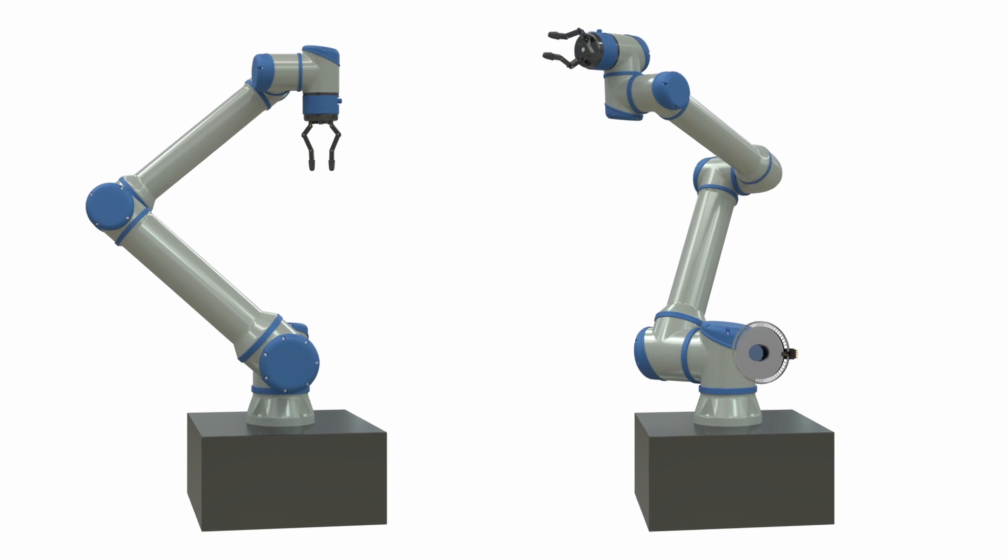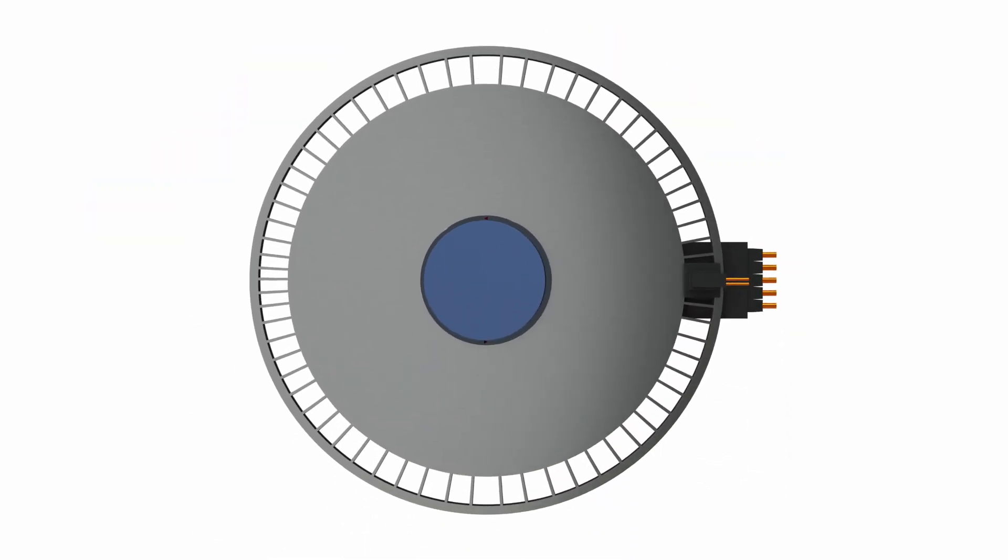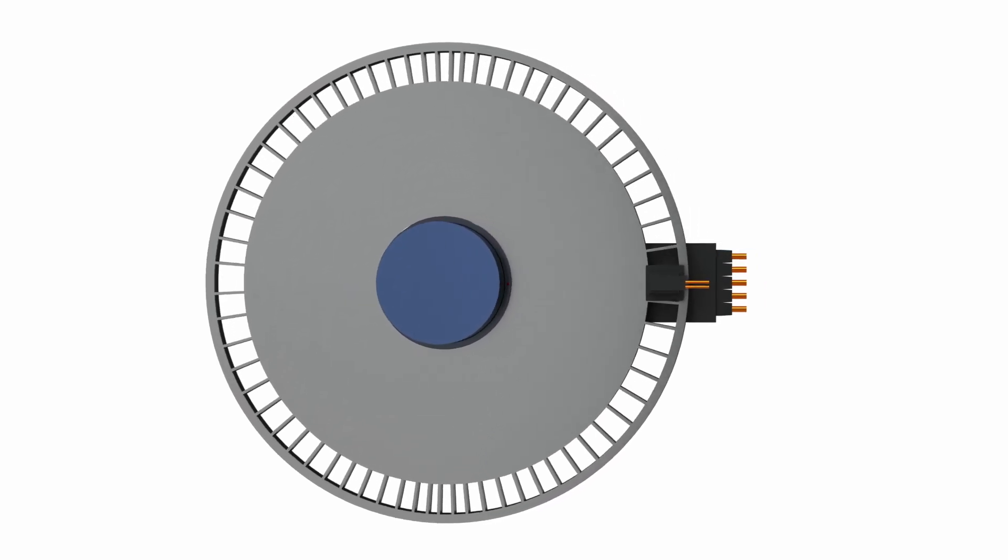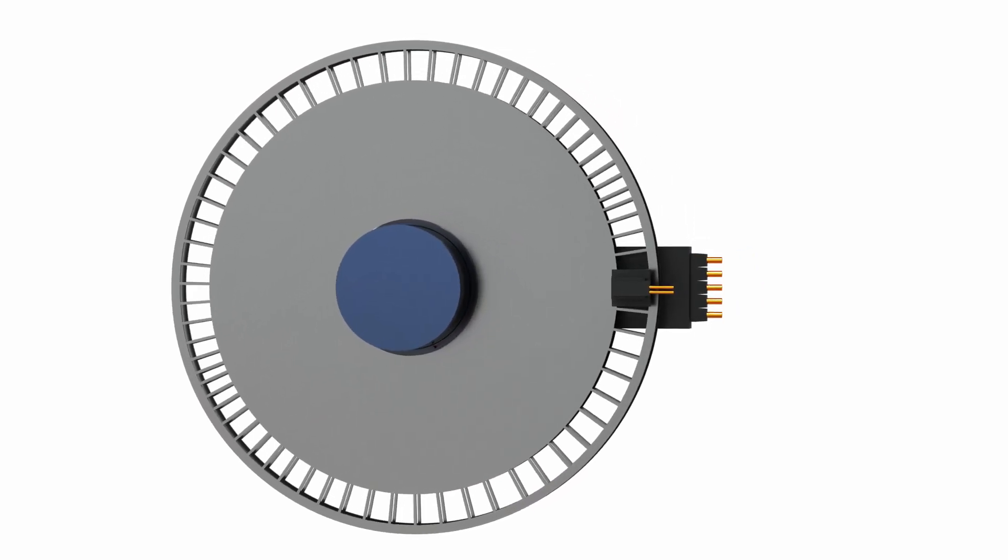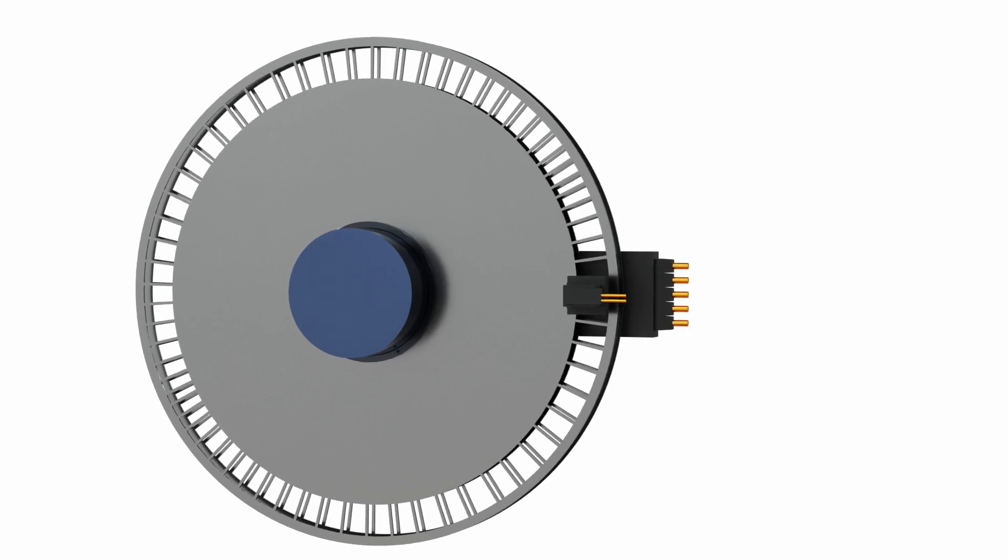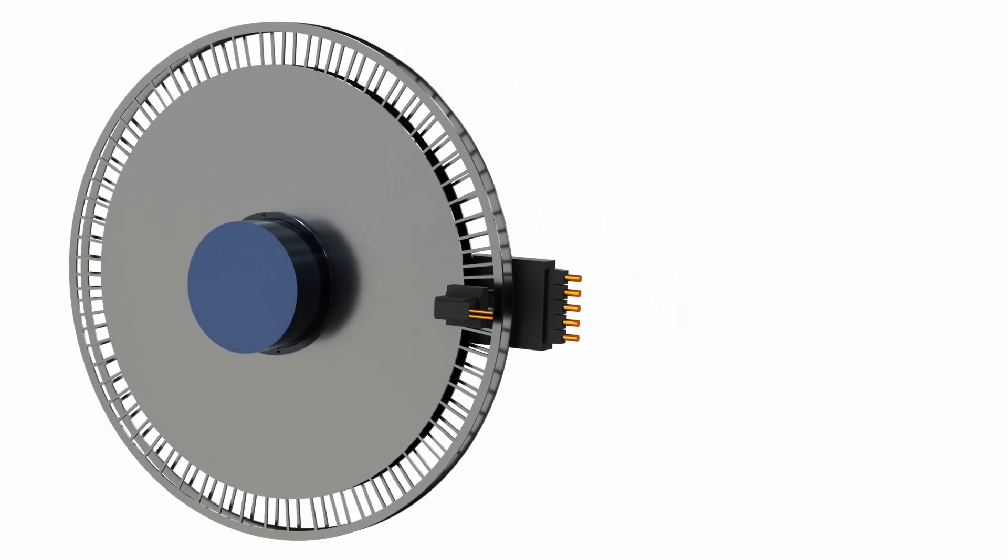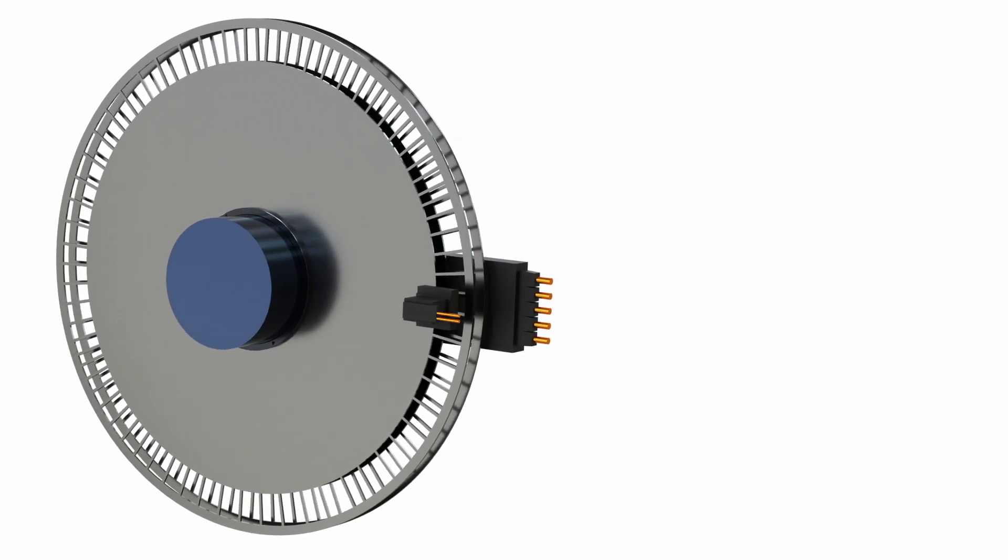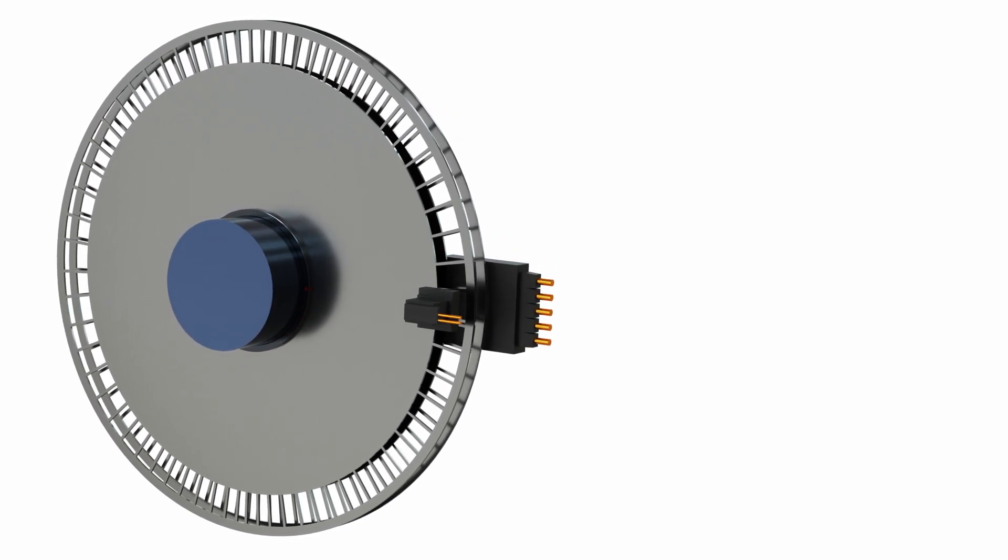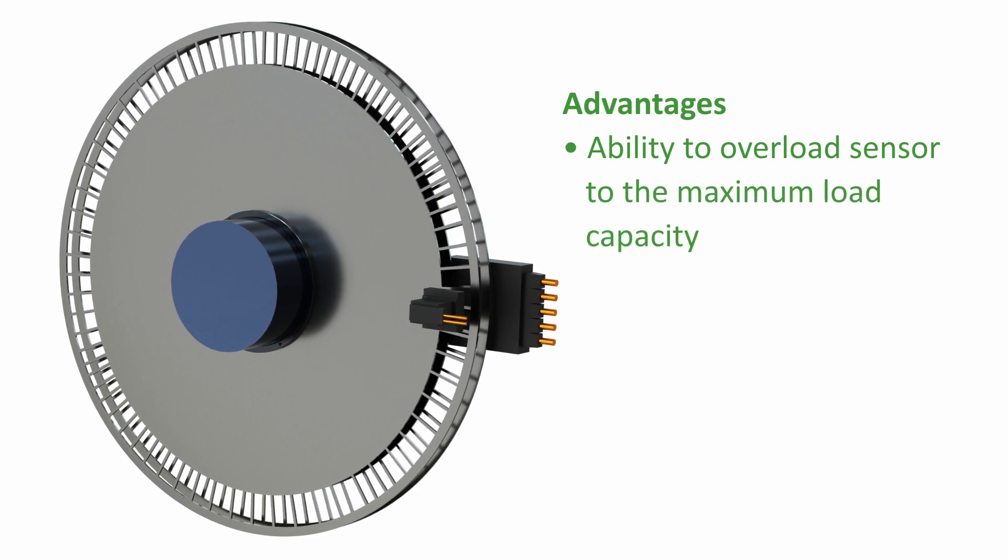Displacement sensors: this method typically uses a pair of measurement discs attached to opposite ends of a shaft. The twist angle of the shaft is measured from the phase difference between the discs through an optical or magnetic measurement. This enables torque to be calculated. The main advantage is the ability to overload the sensor to the maximum load capacity of the twist shaft.